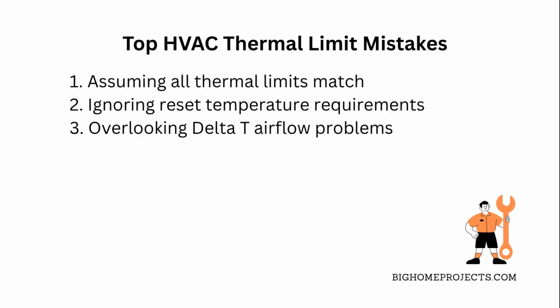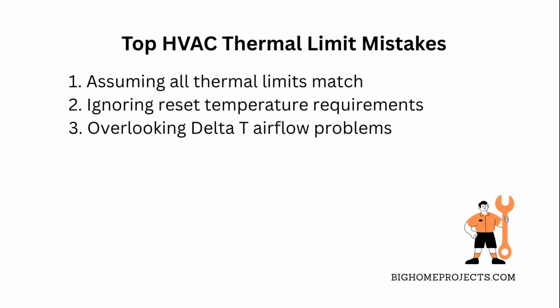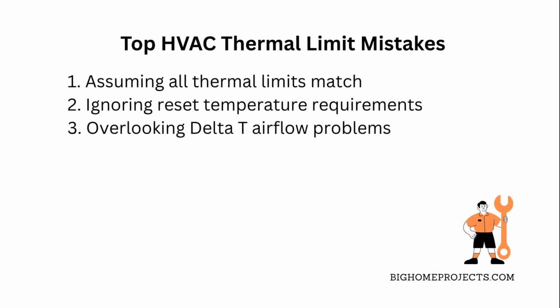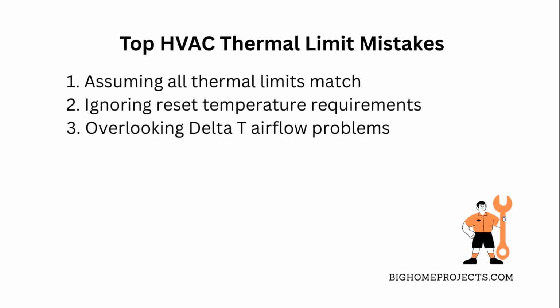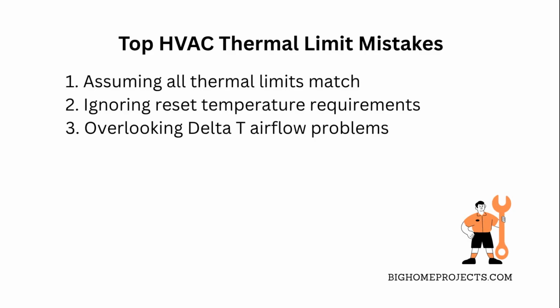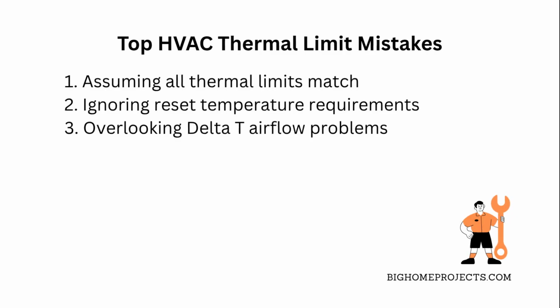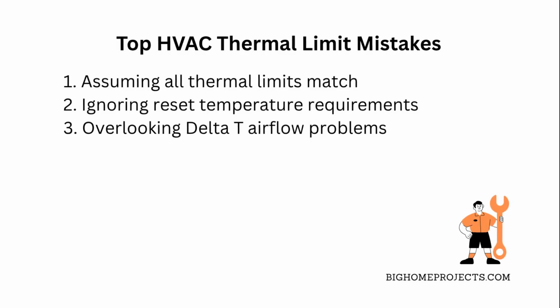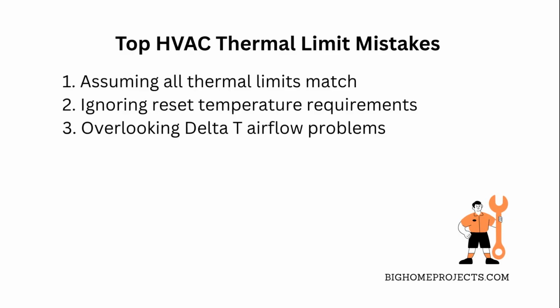One of the biggest mistakes HVAC techs make with electric strip thermal limits is assuming all limits open at the same temperature. Some might be different, so always check the manufacturer's specs before replacing. Another issue is not factoring in the required temperature drop before the limit resets. If you replace a limit that closes at a higher temperature than needed, it can cause the strip to cycle too fast or not reset properly. Lastly, ignoring Delta T readings can lead to missing underlying problems like airflow issues or dirty filters, which put extra strain on the system and cause thermal limits to trip unnecessarily.